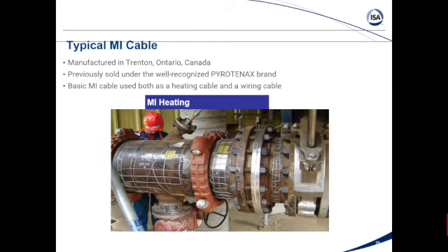The problem is the self-regulating cable, even if it gets very hot, it will still put out power. So if you took, for example, a 1-inch diameter copper pipe, and you put on our minimum output cable, which is 3 watts per linear foot, and you let it cook, no control, it can easily get the temperature of that pipe up to 120 degrees. So I've gone to plants and I've seen them test it, and they pull the chain to test the safety shower, and steam has come out.